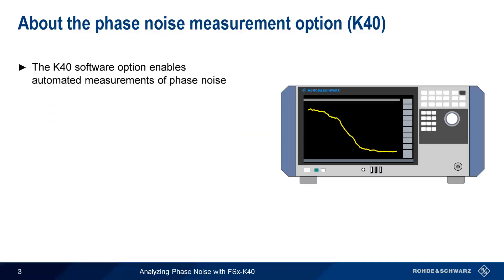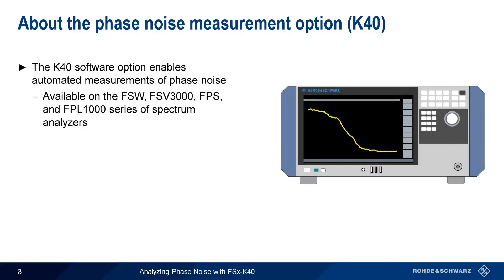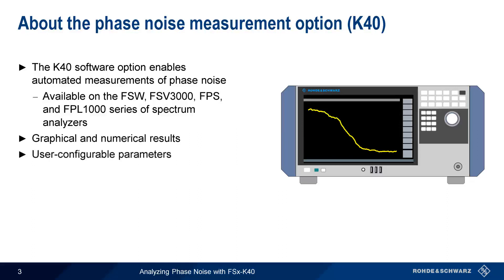The K40 phase noise measurement option enables simple, automated measurements of phase noise and is available on the FSW, FSV3000, FPS, and FPL1000 series of spectrum analyzers from Rohde & Schwarz. In this presentation we'll be using an FSW, but the GUI and functionality is essentially identical across all instrument families. The K40 option provides both graphical and numerical results and allows the user to configure a wide variety of measurement and analysis parameters, including a variety of more advanced features.